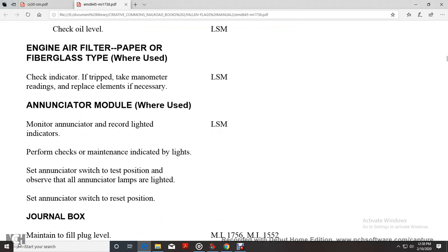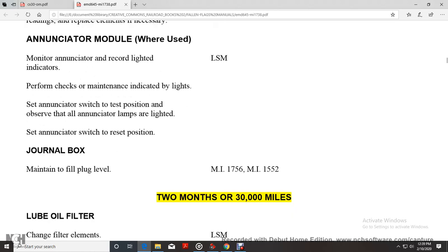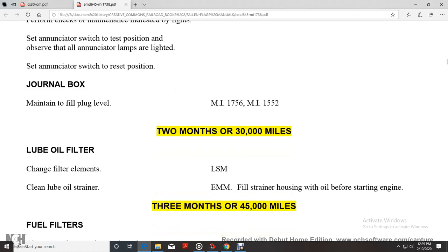Annunciator module where used: monitor annunciator records, lighted indicators, and check for the maintenance indicating lights. If set, annunciator switch to test position, observe all of the annunciator lights are lighted, and set the annunciator switch to reset position. Journal box: maintain fill plug level, maintenance instructions 1756 and 1552. 2 months or 30,000 miles. Lube oil filter: change filter element, locomotive service manual. Clean lube oil strainer, electric engine maintenance manual. Fill strainer housing with oil before starting the engine.